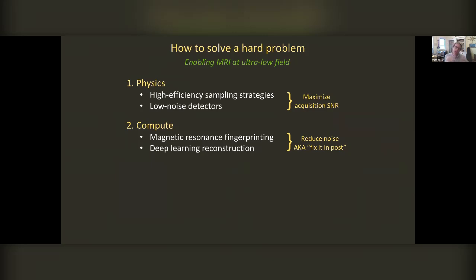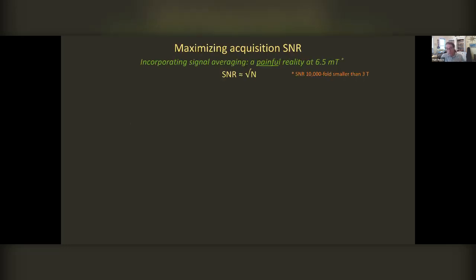You could think of the physics as how you can interrogate the system so that you maximize your acquisition SNR, the SNR in your preamp, let's say. And then once you acquire that data, what can you do to reduce the noise, or what the kids call fixing it in post? Now, all of you know that you're going to have to do signal averaging. Again, the story I'm telling is about 6.5 millitesla. Some of these things translate to the Hyperfine scanner, some don't, so please take them on their own.